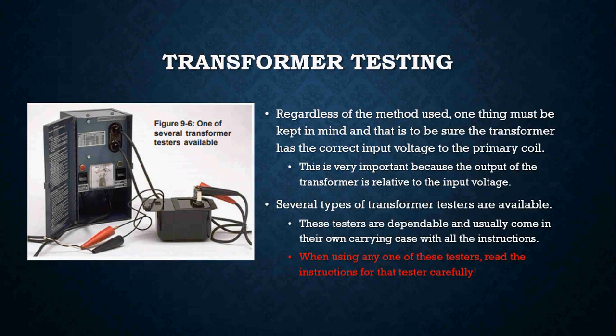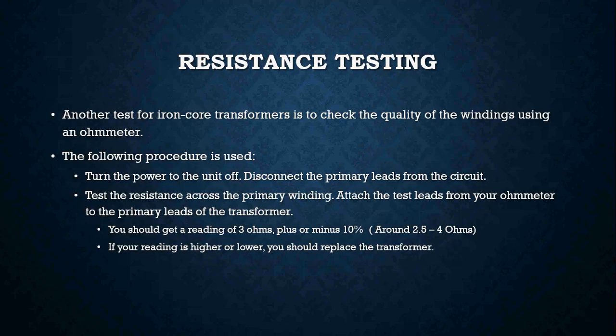Now, testing transformers, there are a lot of different methods of doing it. But one thing you must keep in mind when testing these transformers is to make sure you have the correct input voltage to the primary coil. This is very important because the output of the transformer is relative to the input voltage. There are several types of transformer testers available. These testers are dependable and usually come in their own carrying case with their own set of instructions. You must read those instructions carefully to make sure you're using the tester correctly and that it's meant for that particular type of transformer.